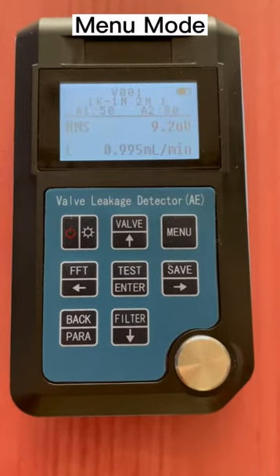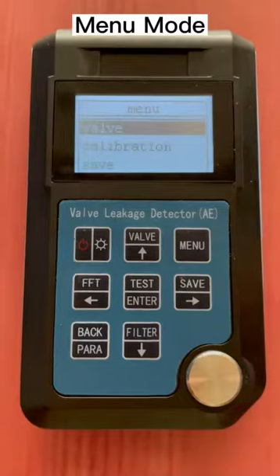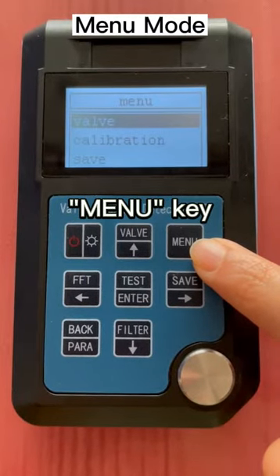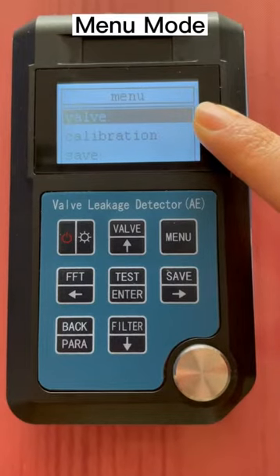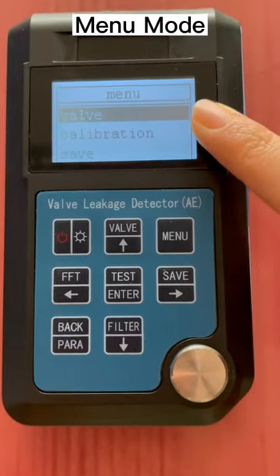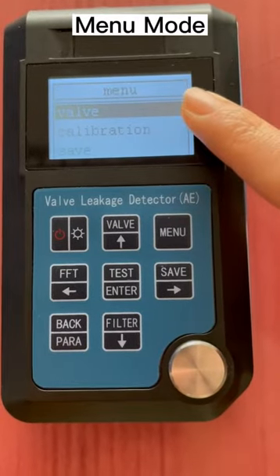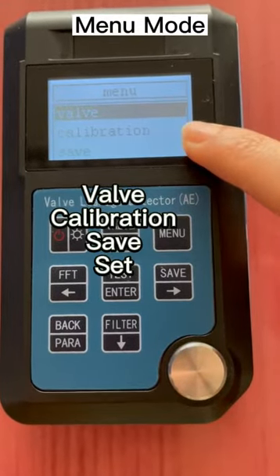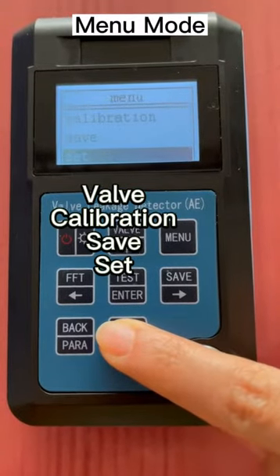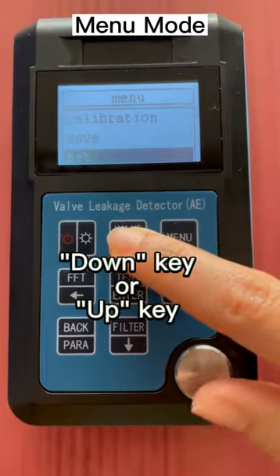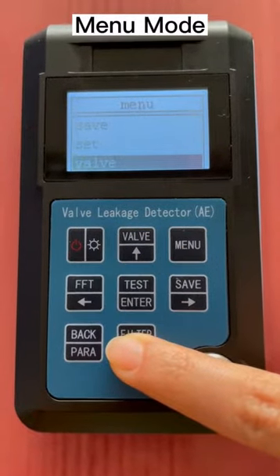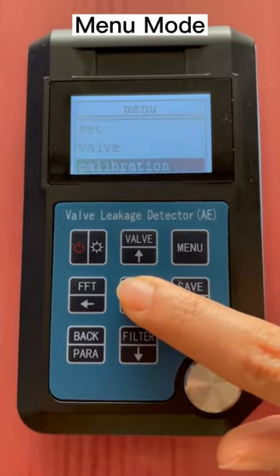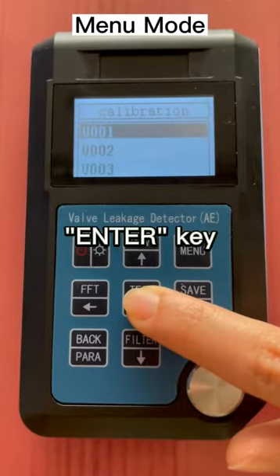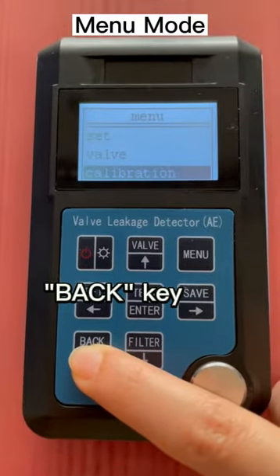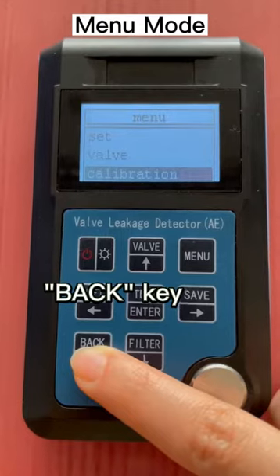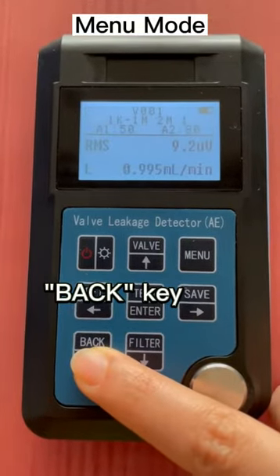Next, we will introduce the functions in menu mode. Press the menu key to enter menu mode to view and modify the settings and calibration curves operations. There are 4 options in the menu mode: valve, calibration, save, and set respectively. Press the arrow up or down key to move the cursor. Once the cursor is on the selected option, press enter to enter the submenu. Press the back key to exit the current menu and return to the upper menu level, or back to the test mode.